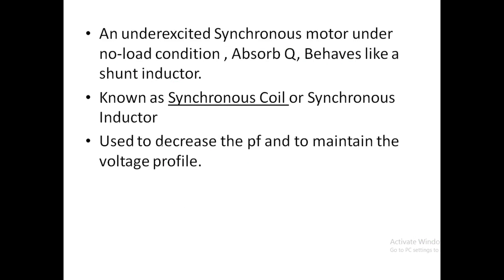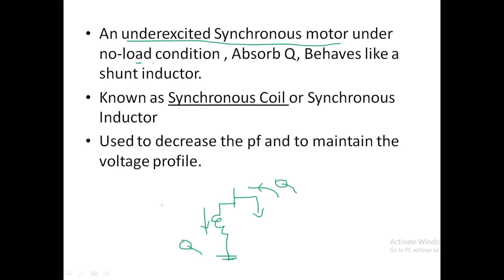Sometimes the load may be more capacitive — this is actually very rare. A capacitive load delivers reactive power rather than absorbing it. That reactive power has to be absorbed, so we connect a shunt inductor. Similarly, an under-excited synchronous motor under no-load condition absorbs reactive power and behaves like a shunt inductor. This is known as a synchronous coil or synchronous inductor.